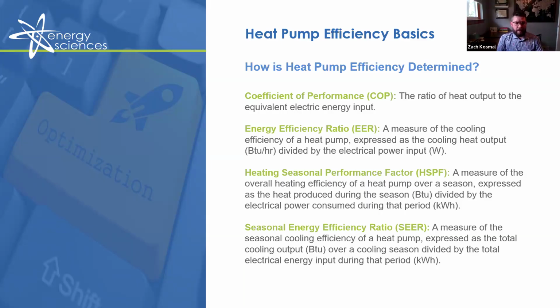And interestingly enough, SEER was recently replaced with SEER 2, not to make things more complicated, but SEER 2 is now the official standard of efficiency ratings since 2023. And the key difference is that SEER 2 accounts for more real world conditions, such as ductwork resistance and static pressure within that system. So SEER 2 is typically a bit lower than your original SEER. So for example, a 14 SEER unit may be rated around 13.4 for SEER 2 rating. Okay. And we will expand on these efficiency metrics a little later on in the presentation, and I'll touch on how to compare them and when each efficiency metric is most useful.